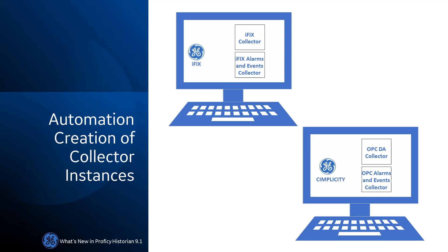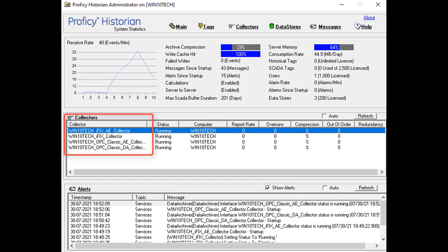Automatic creation of collector instances. When you install collectors, if iFIX is installed on the same machine as the collectors, one instance each of the iFIX collector and the iFIX alarms and events collector are created automatically. Similarly, if CIMPLICITY is installed on the same machine as the collectors, one instance each of the OPC Classic data access and OPC Classic alarms and events collectors for CIMPLICITY are created automatically. You can begin using these collectors or create more instances as needed.